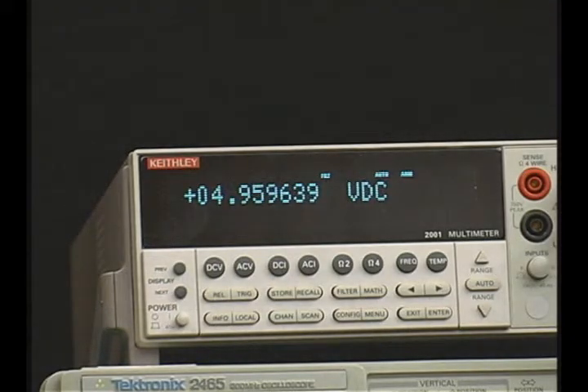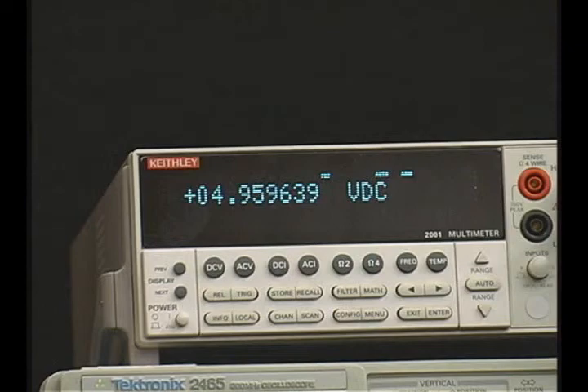It's important to note that Keithley's 7.5-digit multimeter, demonstrated here, is in fact one of the most capable meters ever produced. However, when this or any other testing device is misapplied for the detection of aging intermittent problems, then it is the fault of the test engineer and not the equipment manufacturer. Generally, the higher the accuracy of a digital multimeter in digits to the right of the decimal will equate proportionally to its lack of speed to catch a random intermittent. It's simply the wrong approach for this problem.